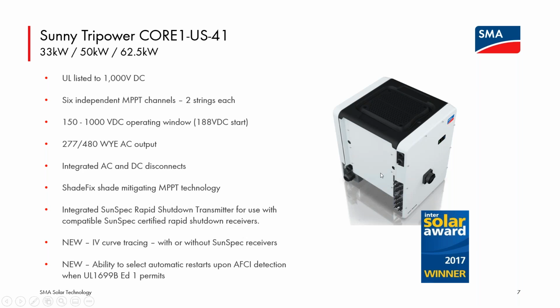So there is flexibility in terms of string length, design, module orientation, and module power class. We're seeing, I think, great interest in bifacial modules that are getting to higher power and also high current. So when we show the spec sheet, quite often we're finding people can get a good DC to AC ratio on the CORE1 with those newer high current modules using one string of modules per input. And the nice thing on the CORE1 is you can drive a tracking channel input fully through a single positive and negative connector for that input, even though two are provided on the inverter. And I'll try to reemphasize that a little bit, make it a little more clear on the spec sheet slide.